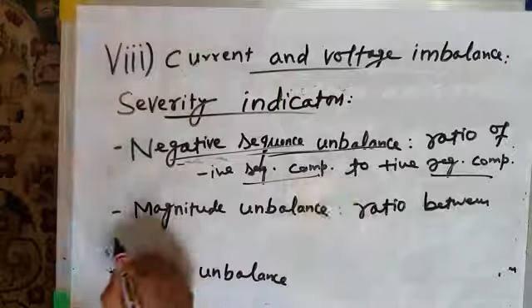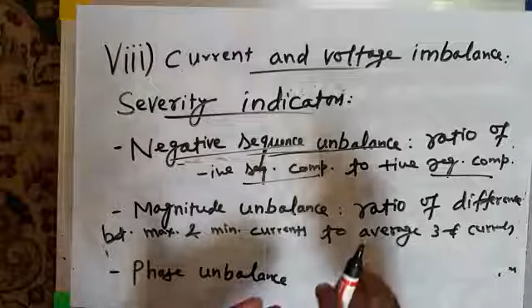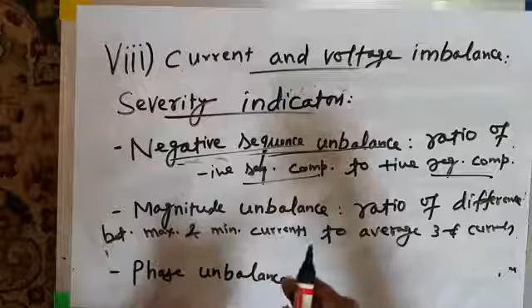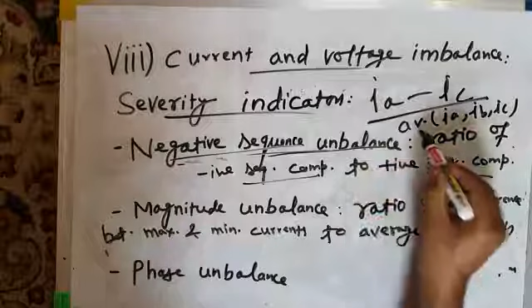Second is magnitude unbalance. Magnitude unbalance is defined as the ratio of the difference between maximum and minimum line currents to the average line current, or average three-phase current. You have three line currents, IA, IB, IC. Their magnitudes are different. You first find the minimum magnitude and the maximum magnitude. One line's current will be minimum, another phase's line current will be maximum. Find the difference between them. Let us suppose IA is maximum and IC is minimum. So IA minus IC, divided by the average of IA, IB and IC. That is the difference between maximum and minimum magnitude, divided by the average of the three phase currents. This gives another severity indicator, magnitude unbalance. The higher this ratio, the higher is the unbalance in the currents.